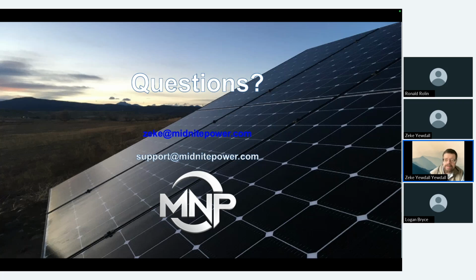However, there's a couple different reasons to get to 100% state of charge regularly. Lithium, we got away from having to get to 100% all the time to prevent sulfation, because that was a big issue with lead acid batteries that we recommended always getting up to 100% once a week. Lithium stopped that, but there's still the balancing issue and the state of charge drifting issue. I would say for the balancing issue, it's probably a little less important to get the PF16s up to 100% regularly. But for the state of charge drifting issue, I would still try to get them up to 100% once every week or two. This is usually off-grid systems in the wintertime where they're just not getting full regularly. I've also seen this state of charge drifting issue on grid tie systems where the settings are such that it never gets up to 100%.